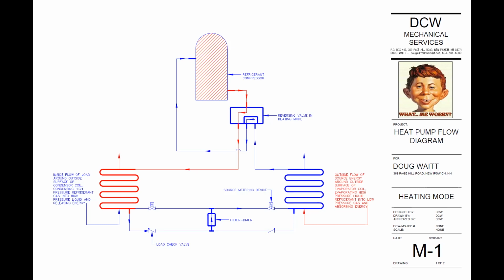Are you saying that the heat pump works when it's minus 13 outside? Yes. That's a cold temperature heat pump. It's always been available, but it's the advent of variable speed compressors that has made that available for us. So you have to order this particular kind? Yes. When I get into the efficiencies of the heat pumps, I'll let you know how that temperature affects things. But yes, at minus 13, I can get, I'm going to use an example.